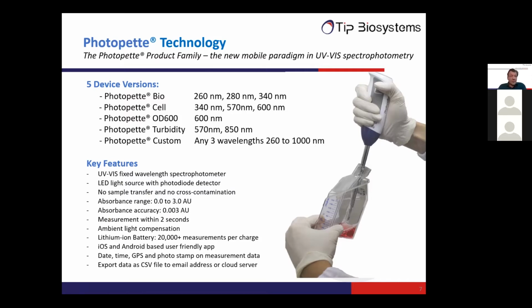I mentioned already it's a UV and visible fixed wavelength spectrophotometer. It has an LED light source. There's no sample transfer, as you have seen. And if you change the tip, there's no cross-contamination. We have a very large dynamic range, up to absorbance units of 3. We achieve this with special algorithms that are used in the instrument. The accuracy is about 0.003 absorbance units.